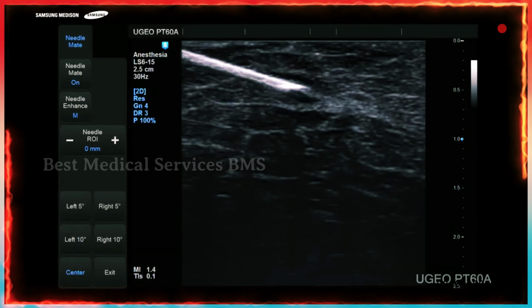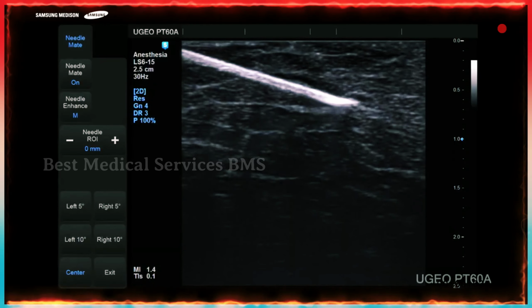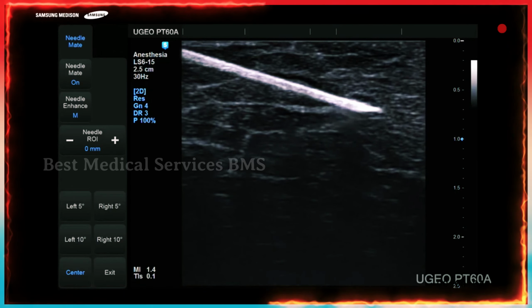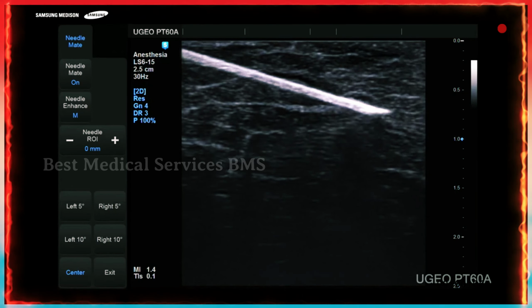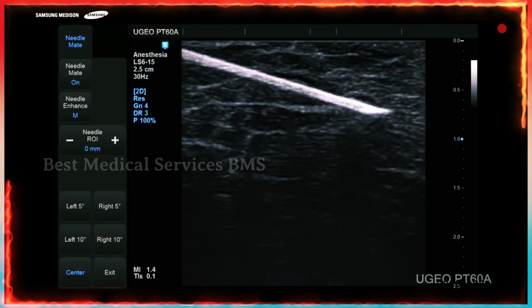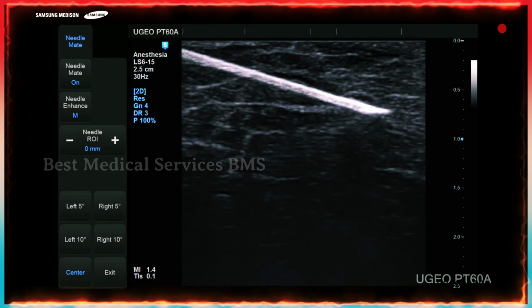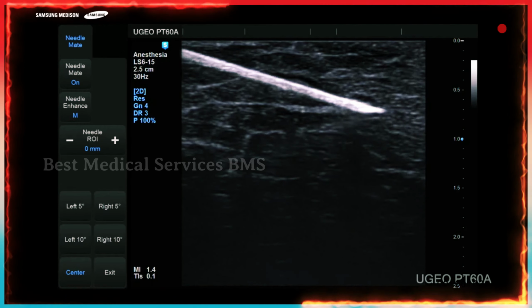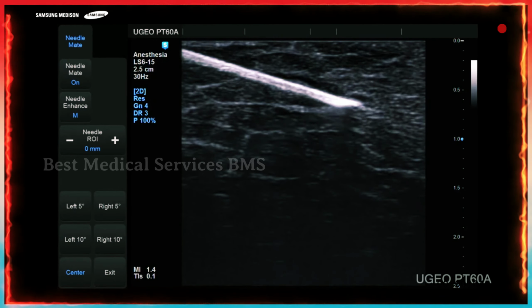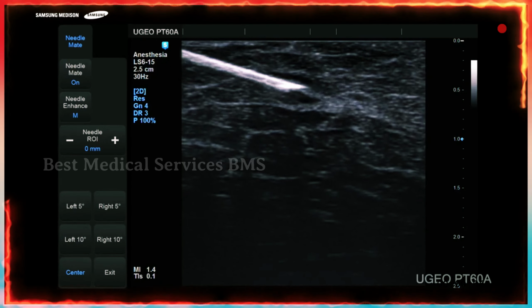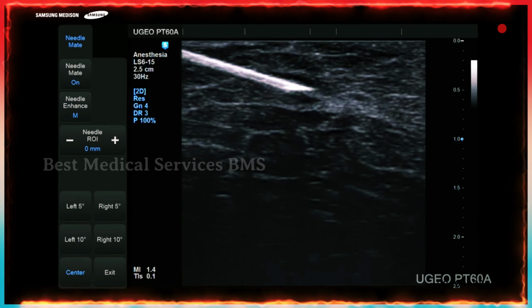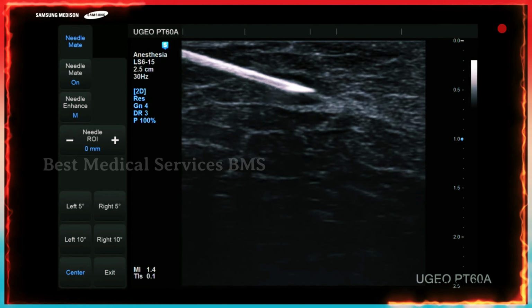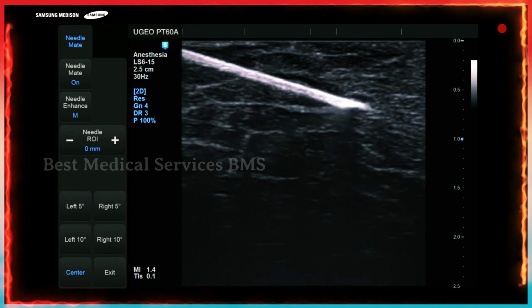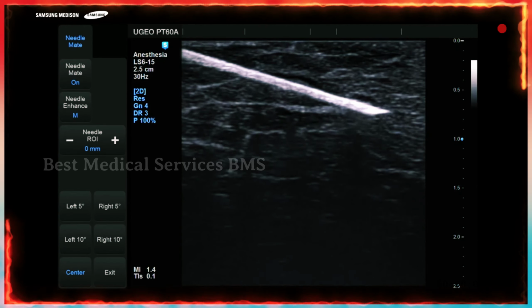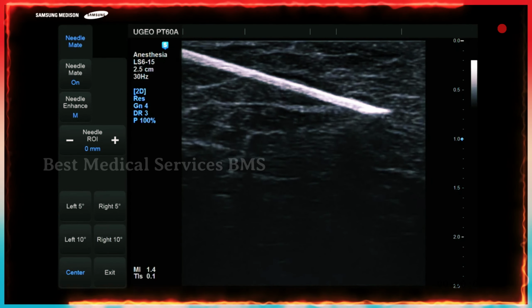Insertion of needle requires clear visualization of the needle tip and shaft prior to injection of local anesthetic. With this ultrasound machine, UGEO PT60A, you can use a needle mate, which is 5 to 10 degrees steering of the rays coming out of the ultrasound probe to the right and 5 to 10 degrees to the left. That's maximum needed to make it clear enough to see the needle.